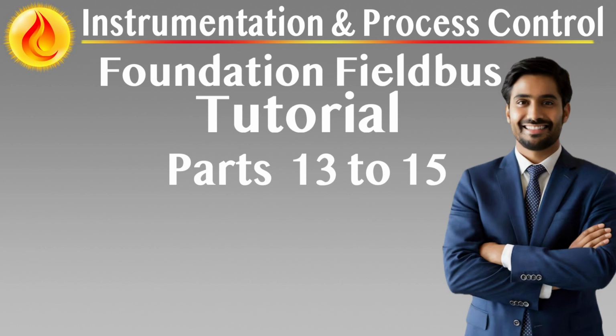Grounding and shielding must be implemented following IEC guidelines and vendor instructions. All device and cable shields must be bonded to a single ground reference. Cabinet, cable tray, and device grounds must be tested to confirm resistance values within specified limits. Floating shields or multiple ground points can induce noise and disrupt deterministic communication.